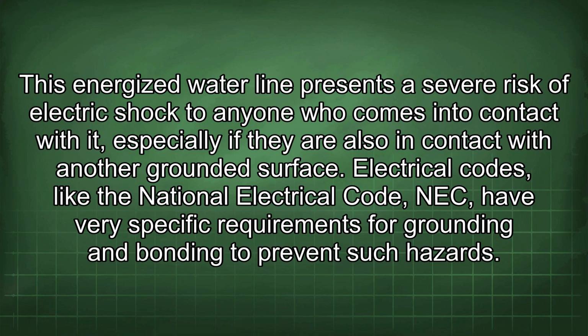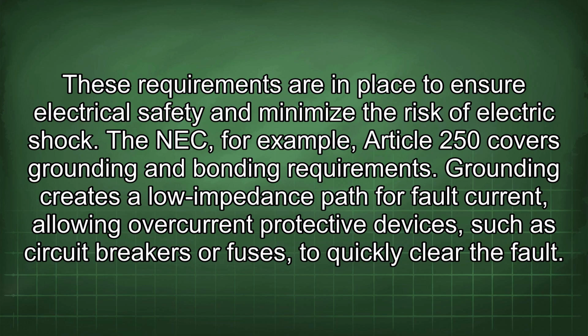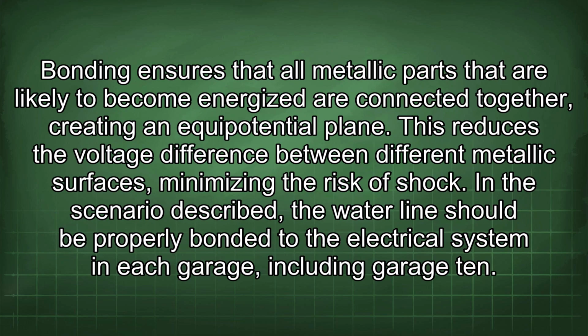Electrical codes, like the National Electrical Code, NEC, have very specific requirements for grounding and bonding to prevent such hazards. These requirements are in place to ensure electrical safety and minimize the risk of electric shock. The NEC, for example, Article 250 covers grounding and bonding requirements. Grounding creates a low impedance path for fault current, allowing overcurrent protective devices, such as circuit breakers or fuses, to quickly clear the fault. Bonding ensures that all metallic parts that are likely to become energized are connected together, creating an equipotential plane. This reduces the voltage difference between different metallic surfaces, minimizing the risk of shock.